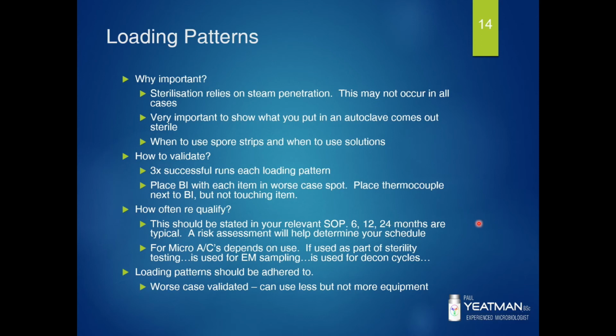For micro autoclaves, that depends on use. So if you're using the autoclave as part of sterility testing, I would suggest you do the validation as often as production would validate their autoclaves, just so there's alignment. If it's used for environmental sampling, whatever you've determined through your validation master plan, and decon cycles typically flow on from the loading patterns. So if you can show your autoclave works for your typical loading patterns, then your decon cycles should be effective. And of course, once you've gone through the effort of validating the loading patterns, they should be documented here too.